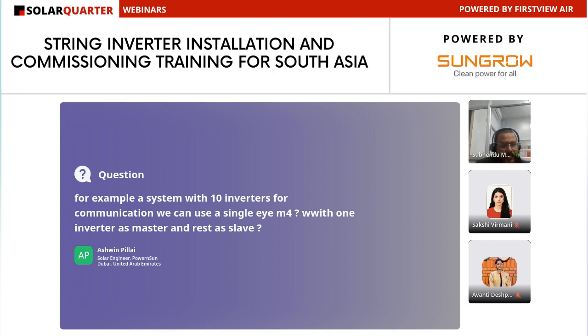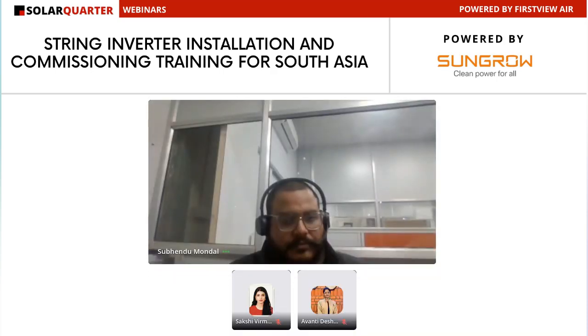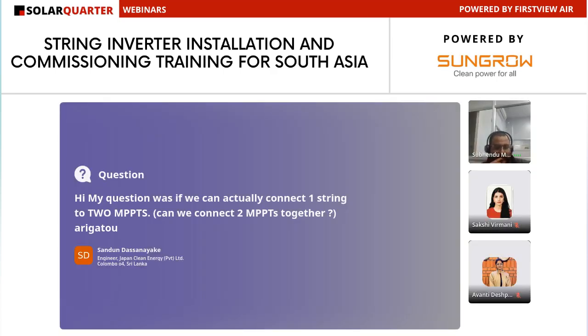For example, a system with 10 inverters, communication via EyeM4, with one inverter as master and the rest as slaves. Yes, one inverter is master and the rest are slaves. Next. Yes, for this case, one is master and the rest are slaves.